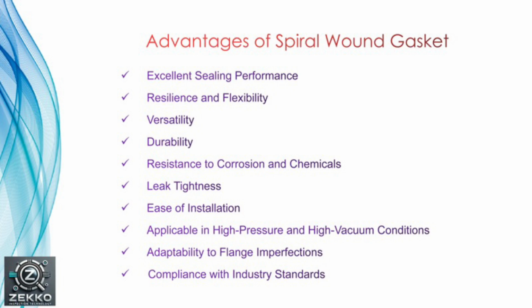They have resistance to corrosion and chemicals. They give better leak tightness performance. They are easy to install, for example in the gap between pipe to pipe, pipe to wall, or pipe to flange. The spiral wound gaskets are also applicable in high pressure and high vacuum conditions. Adaptability to flange imperfection by the spiral wound gasket is much better than other gaskets, and they comply with industry standards, always complying with international standards like ASME B16.20, API 601, and other relevant standards.